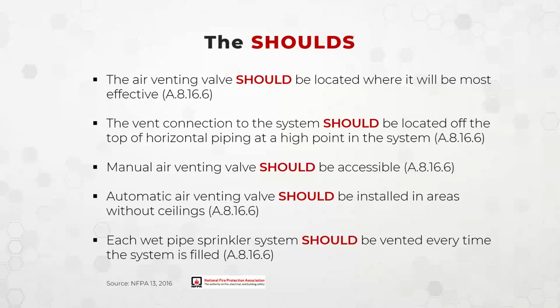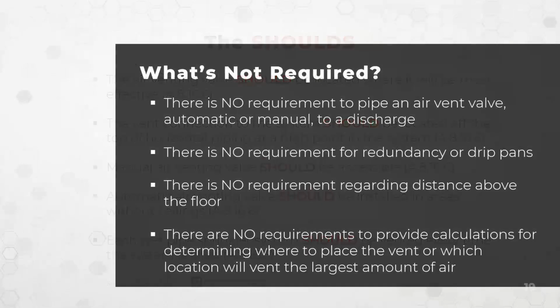And if you're going to put in an automatic air vent, which is far and away the most popular one, you may want to avoid putting it above a drop ceiling or some other structure because all automatic air vents are required to have strainers to protect their mechanism. And NFPA 25 requires in cycle that you be able to clean, flush, and verify the condition of the strainer. So it's just meant as a matter of convenience.